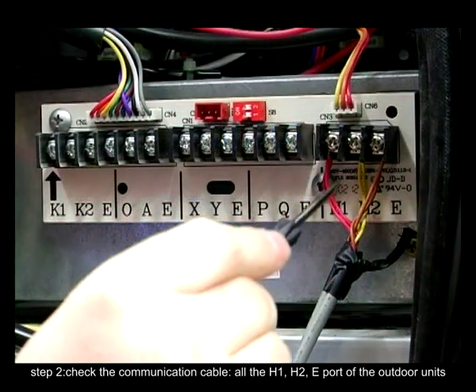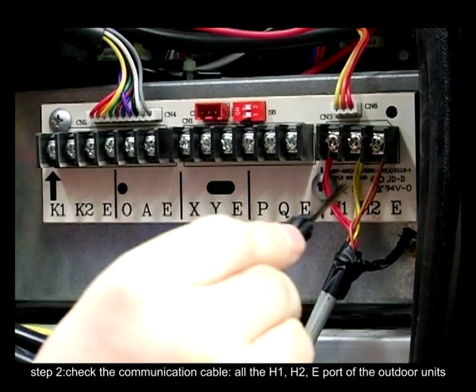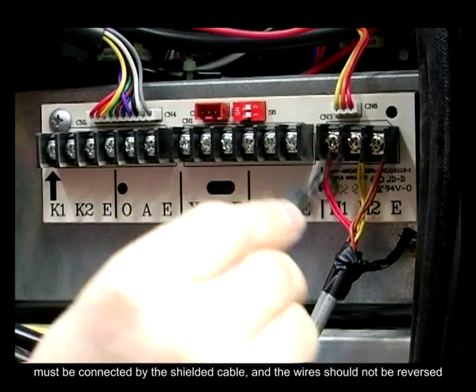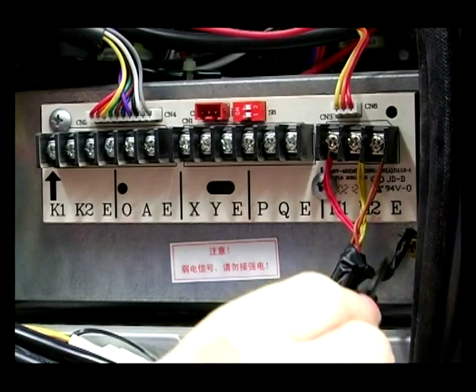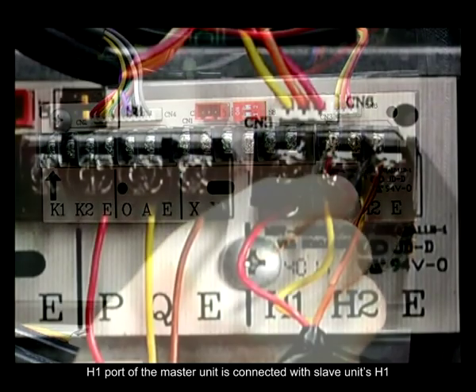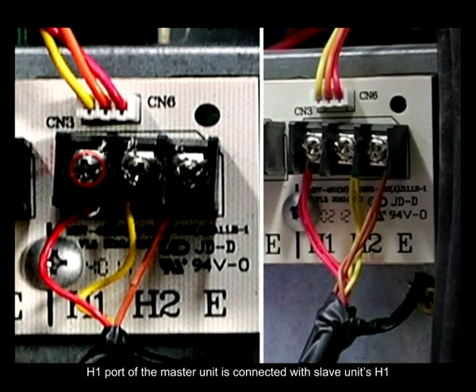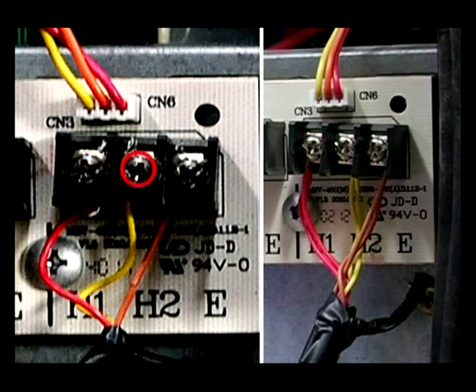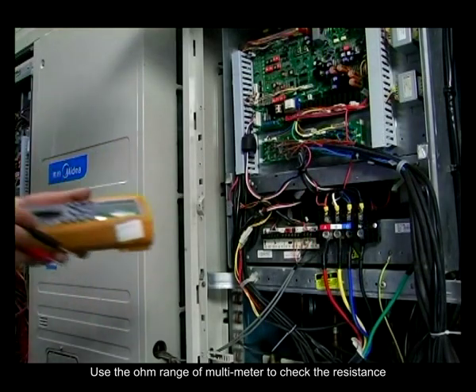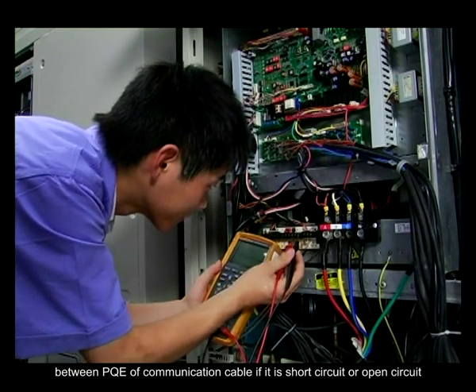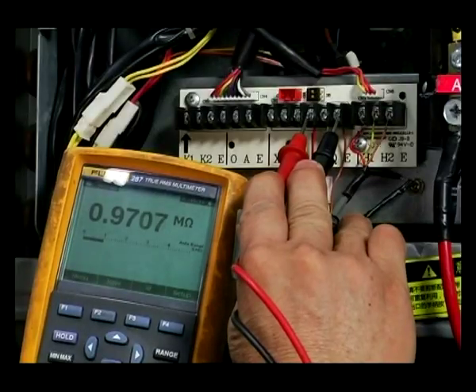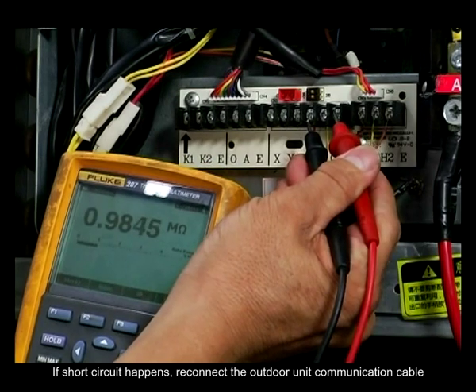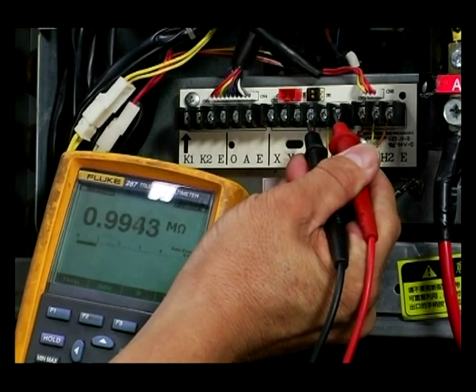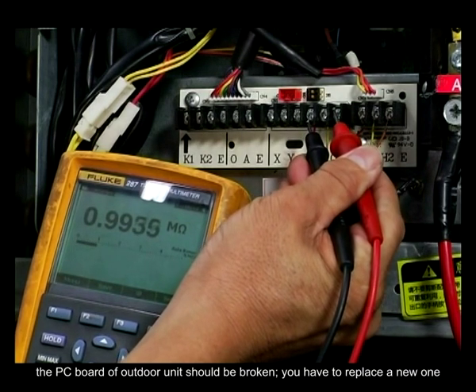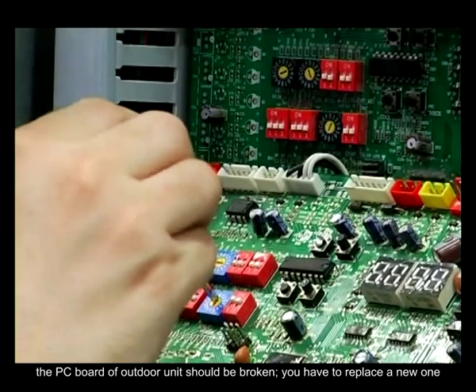Step 2. Check the communication cable. All the H1, H2, E port of the outdoor units must be connected by the shielded cable, and the wires should not be reversed. H1 port of the master unit is connected with slave unit's H1, and H2 port is connected with H2 port. Use the OHM range of multimeter to check the resistance between PQE of communication cable if it is in short circuit or open circuit. If short circuit happens, reconnect the outdoor unit communication cable. After the above repair, if malfunction still exists, the PC board of outdoor unit should be broken. You have to replace a new one.